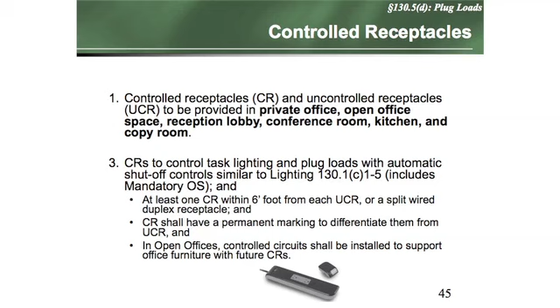Now, if you want to, by the way, you can do the break-off link thing. So I can just bring a switched circuit and an unswitched circuit to the receptacle and do the break-off link. Otherwise, I'd have to have that one and then a green receptacle within 6 feet from it for the control thing. And the code says, by the way, it's whatever's controlling the lighting in the area that controls that receptacle. So in spaces where you had to have an occupancy sensor control the lights, like a conference room, it's got to be the occupancy sensor that now not only controls the lights, but also controls the receptacle in the space. Motel hotels have also got this requirement for receptacles.